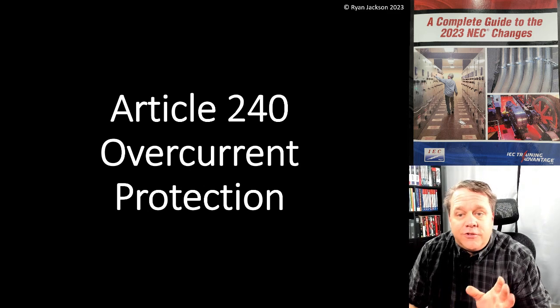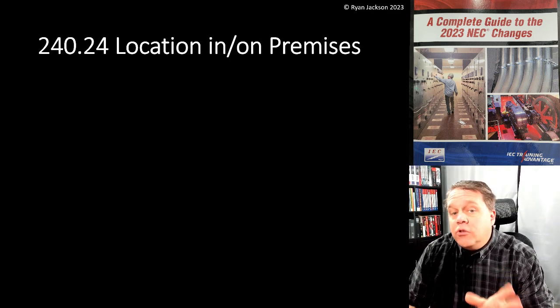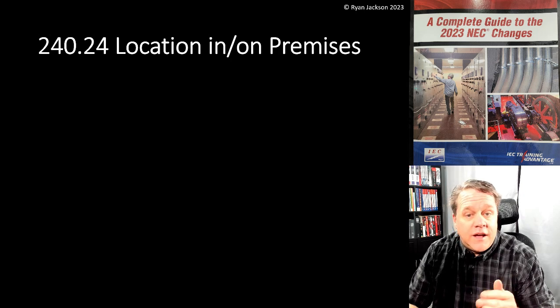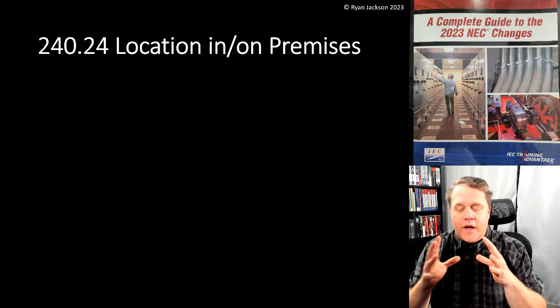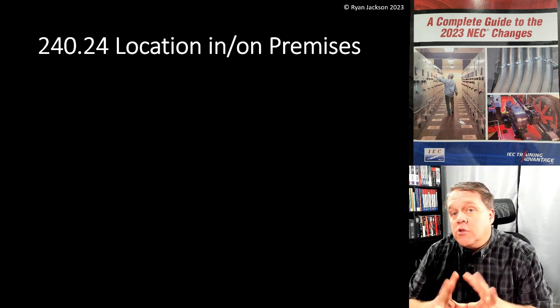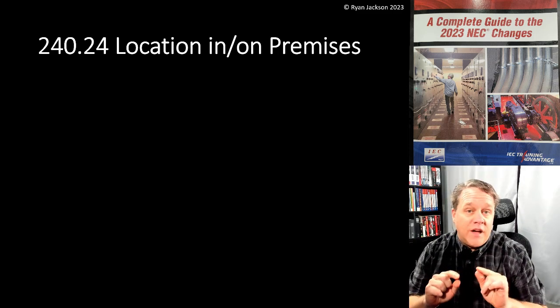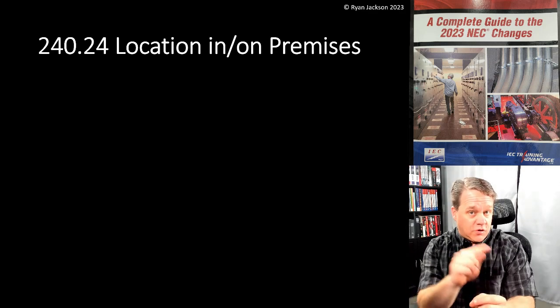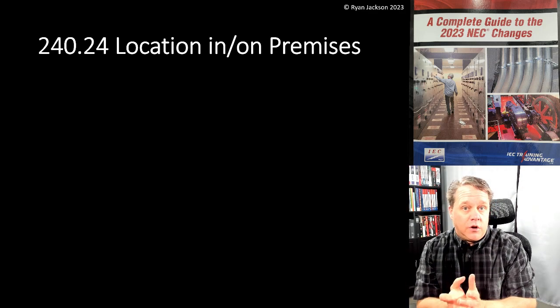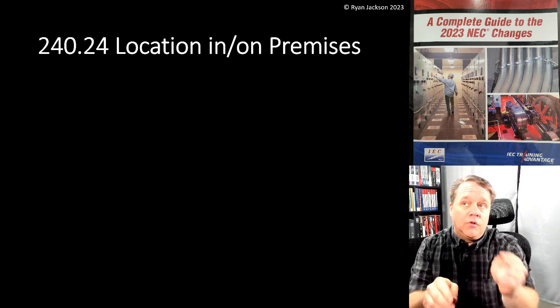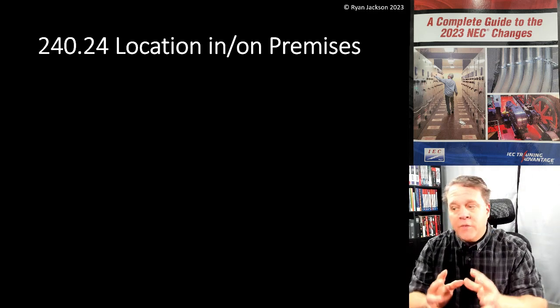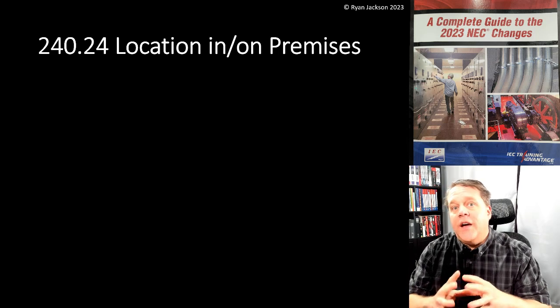Still talking about Article 240, let's discuss 240.24 — location of overcurrent devices in/on the premises. 240.21 talks about the location of overcurrent protection devices as it relates to their location in the circuit — you have to have a circuit breaker or fuse at the beginning of the circuit, or sometimes at the end. But 240.24 talks about the actual physical location within the building.